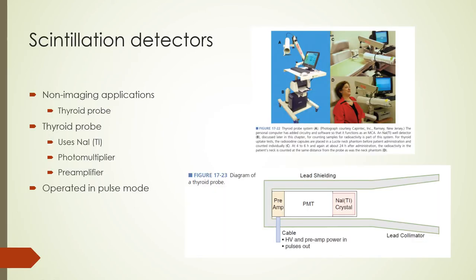In nuclear medicine, scintillators are used in various non-imaging applications, including thyroid probes and well counters. Thyroid probes are used to measure the uptake of iodine-131 or iodine-123 in the thyroid gland. The probe is shielded on all sides and collimated so it records activity coming from only one part of the patient. The probe has a sodium iodide crystal doped with thallium and is coupled to a photomultiplier tube and a pre-amplifier. The signals are sent to a counter for accumulation and display. The photograph shows a typical setup and measurement for a patient.